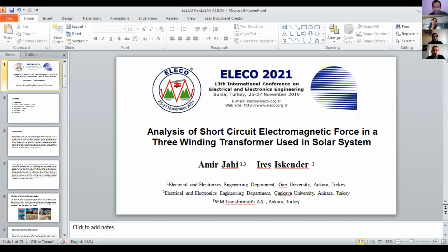Accordingly, in this study, the electromagnetic forces that take place in the winding of a photovoltaic transformer are investigated, and for calculation of these forces, the 3D and 2D models of the transformer are adopted in ANSYS Workbench. The analysis of electromagnetic forces during a three-line fault on the high voltage side of the transformer is performed by the finite element method and compared with the analytical results. The numerical modeling technique discussed in this study would be useful in the design stage of a PV transformer to evaluate the ability of the transformer to withstand the short circuit current.